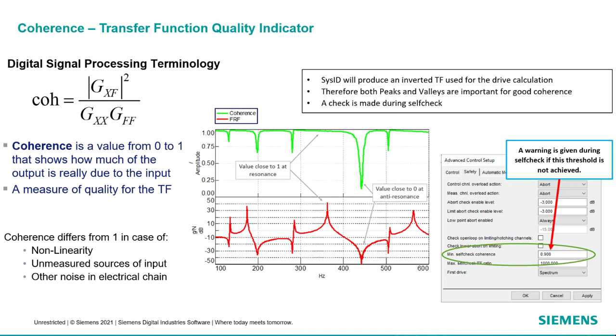So as you build up in drive level, this is the sequence of events from the self-check. You start with basically no excitation to measure the background noise in your system. You want to have that as low as possible, of course, but sometimes there's extraneous noise and maybe some electrical noise that you want to measure also. You don't want that having too much influence on the signal that's being measured. That's also used in the signal to noise ratio calculation further down.